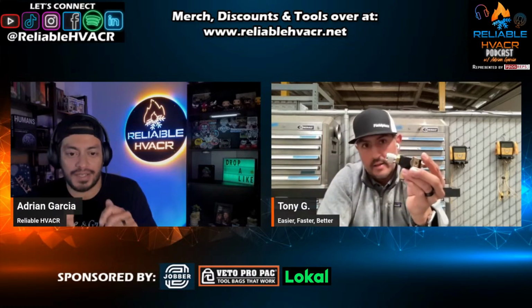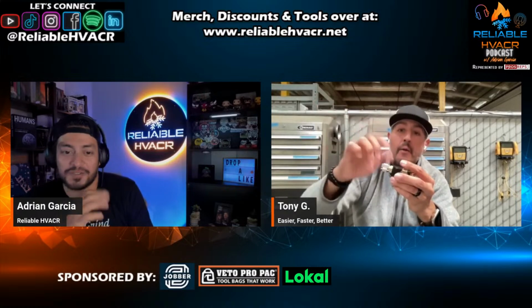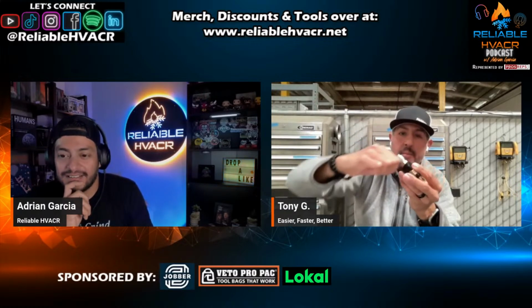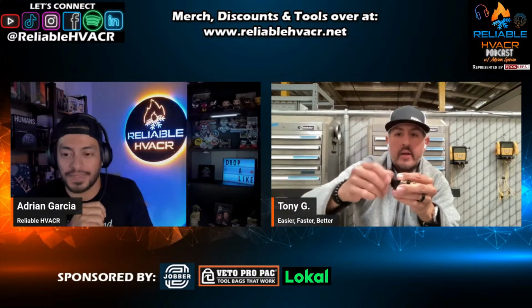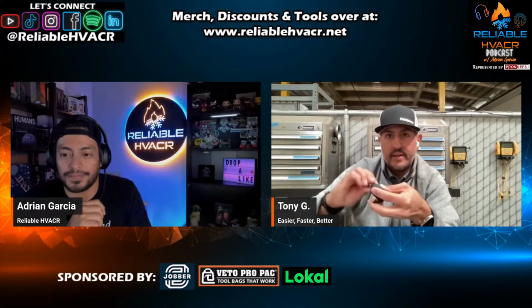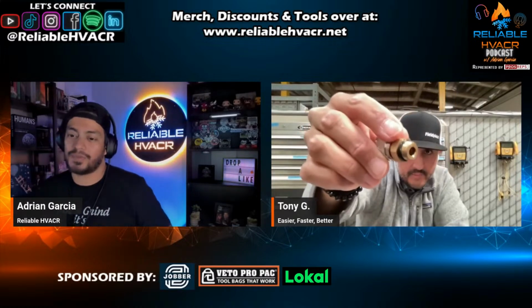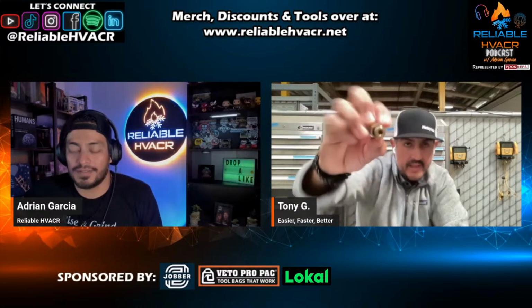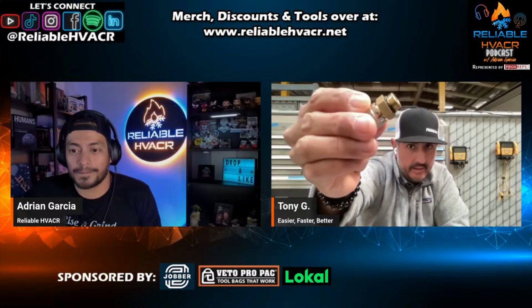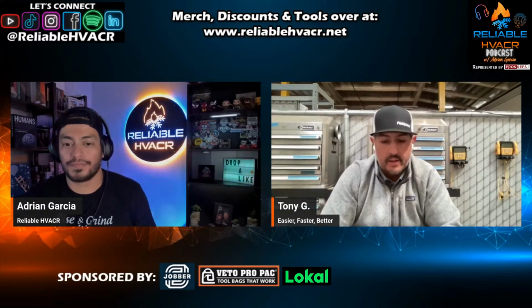So is that just hand tight and you're good? No, I'm just doing this for a demo. I would recommend hand tight and then maybe a 1/4 turn with a wrench. Okay, I gotcha. Oh yeah, for sure. The fitting is wrenched here. Oh, there you go, I couldn't see that part. It's a nut basically, right? Yeah, and so you can just have an adjustable wrench and give it a 1/4 turn. It's got a gasket on it. And the VCR fitting is vacuum rated down to 20 microns, so that's not really something you need to be concerned about.